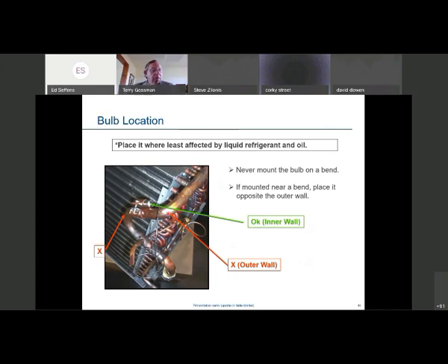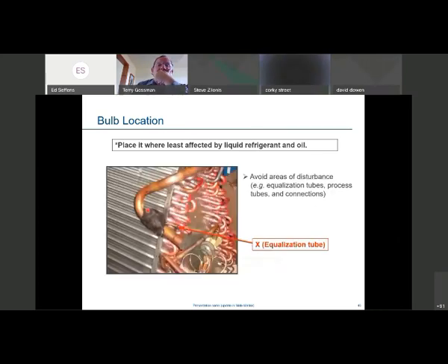Here's another picture of the bulb. Again, it's located at the top. Again, we've got this airflow. This is a coil, but we've got this airflow going up. It could hit this. Again, I would probably insulate that, keep that away from the airflow. There it is. We took that one step further and we've insulated it. So I knew that was coming up.